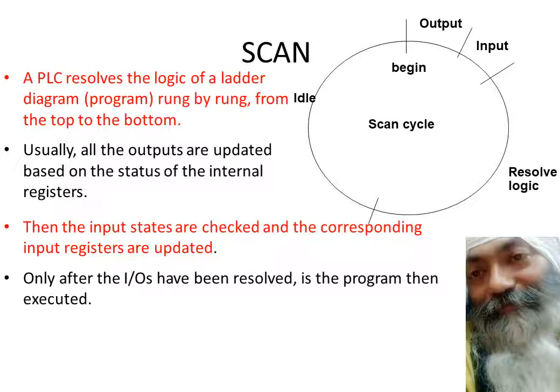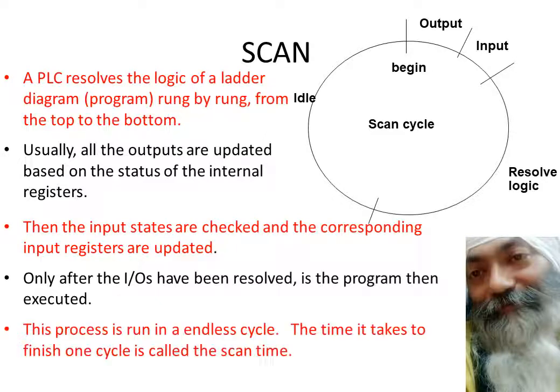Only after all IOs have been resolved, the program is executed, the output is given to the field, the input is taken from the field, and the program is then executed. When I say program, it means the user program, which is programmed by the user, normally in the form of ladder diagram. So this process runs in an endless cycle. And the important point to note is that the time it takes to finish one cycle is called scan time. We will discuss more about scan time in the following slides.